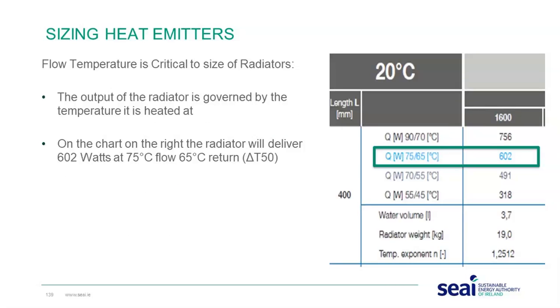So on the chart on the right, we can see with a flow temperature of 75 degrees and a return temperature of 65 degrees, that radiator, which is a 400 by 1600. If we look up this chart, this is a snippet from a radiator manufacturer's chart. This is how they demonstrate it, and it will show that that radiator will deliver 602 watts, which would be typically at a delta T of 50 degrees.